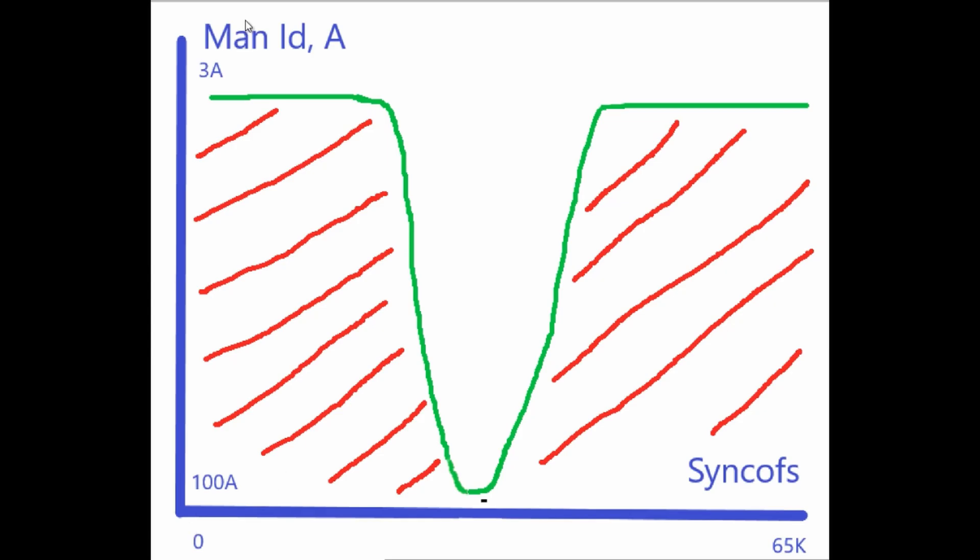Now just a quick few words about strategy for sync-offset tuning. Effectively what we will do, we will start from very low coefficient close to 0 and we'll start increasing it. What we will find that to make motor move, we'll have to increase the current. Higher the sync-offset value is, the higher current is required to move the motor. At some point, increasing current further will not move the motor. This is really the point where we're looking for. This is the perfect alignment of magnetic fields that we require. But then if we increase the sync-offset further, we will get that basically motor will start moving with a lower current, but in opposite direction.